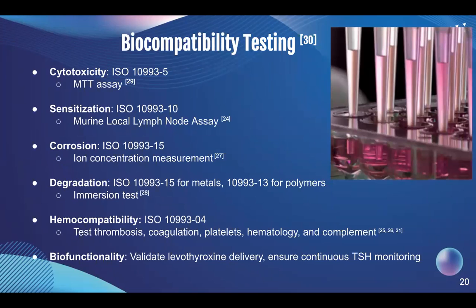The standards for the testing methods are listed on this slide, and I'm going to go into detail for each of them. For cytotoxicity, MTT assay would be done by direct contact, which is both quantitative and qualitative, and this will be done to measure cell proliferation and viability. This method has high accuracy at detecting cytotoxicity and is the most common method.